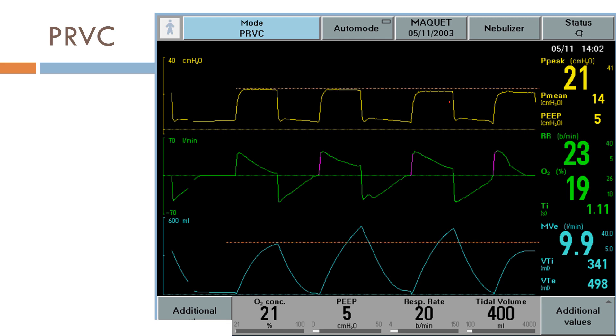Here's another quick example. Here is 400 milliliters as indicated, and here's the pressure. We have a pressure delivered and our volume is a little bit below the target. The second breath, we increased the pressure a bit, but the volume went above our goal. So the next breath, the pressure is reduced, but our volume is still above 400 milliliters. So again, the pressure is going to be reduced and we are now below our target. As you can see, with time the pressure is decreasing.